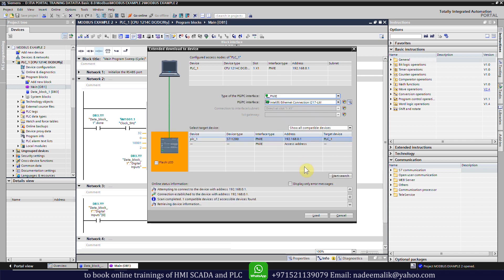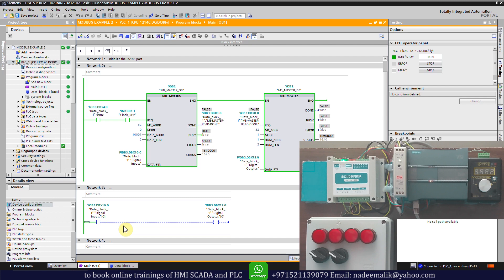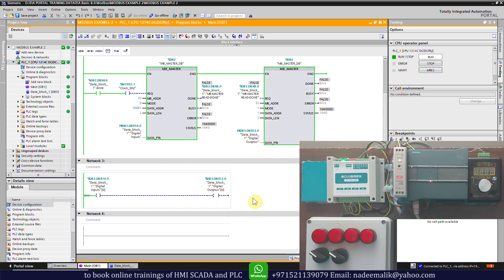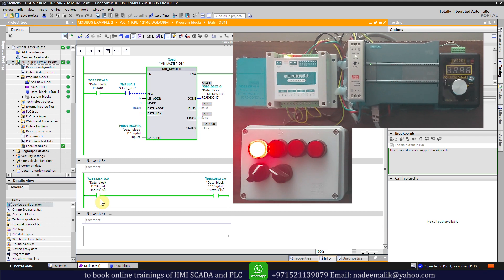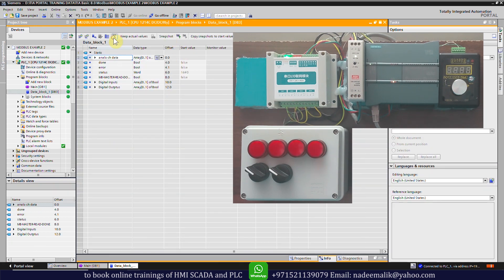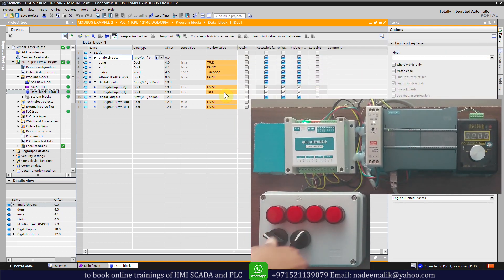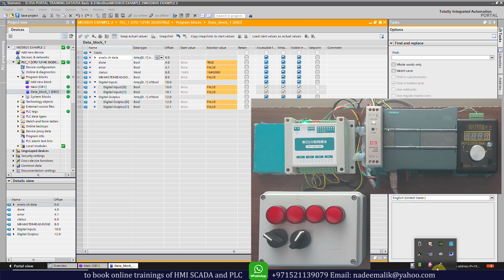We will upload this program into the PLC and monitor the logic. Both the read and write functions are working properly. If we turn on the switch connected at digital input 0 it will close the contact, turn on the digital output coil, and the LED will turn on. Opening data block 3 to monitor the tags, we can see that turning on digital input 1 sets its tag to true, and turning off the selector switch sets it back to false.